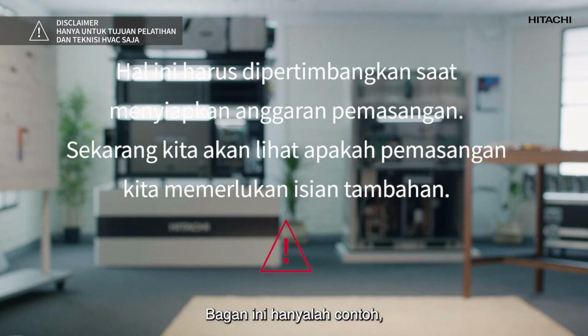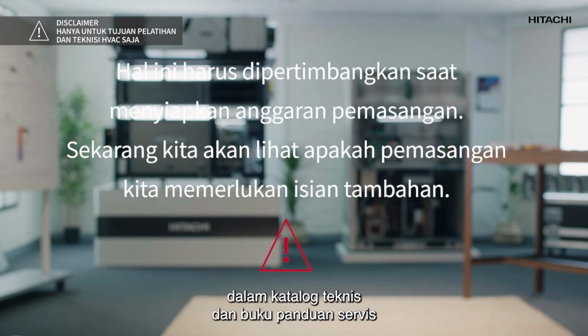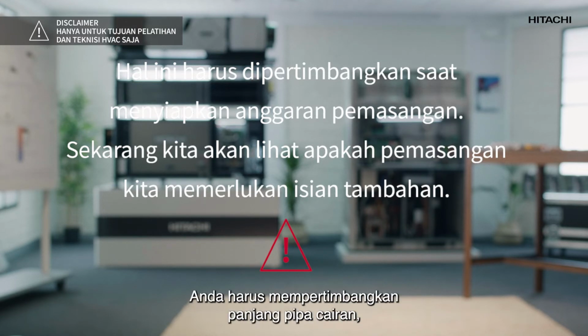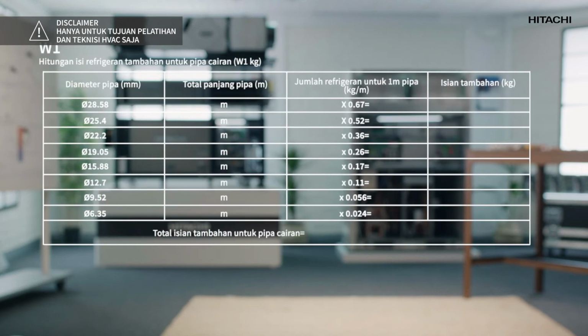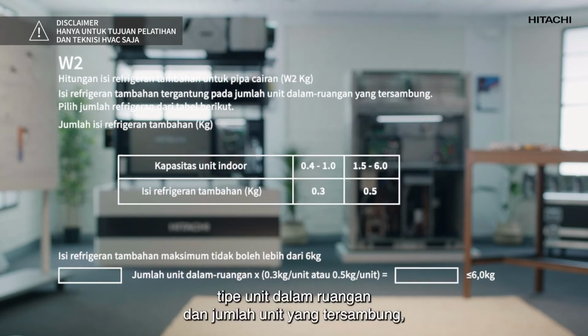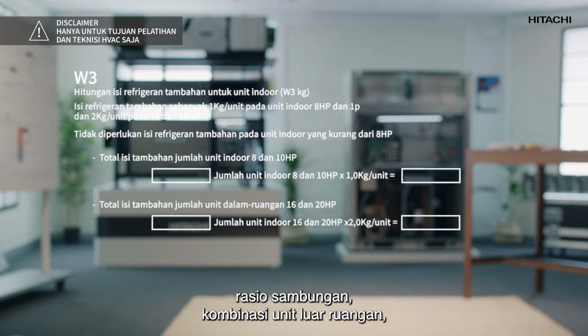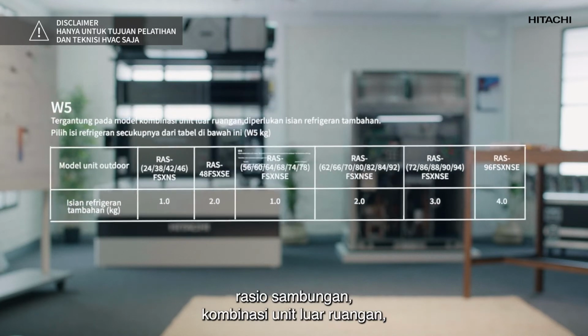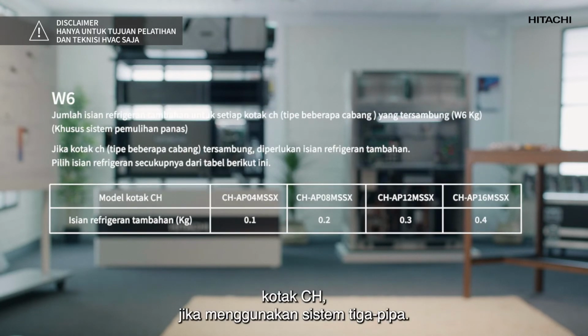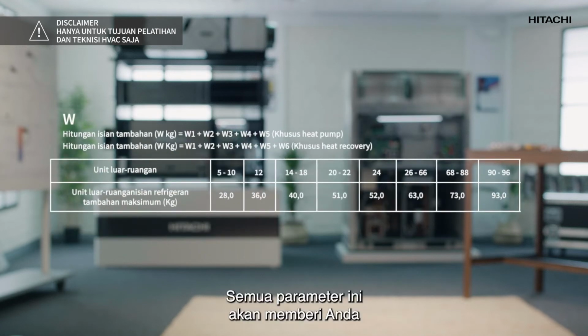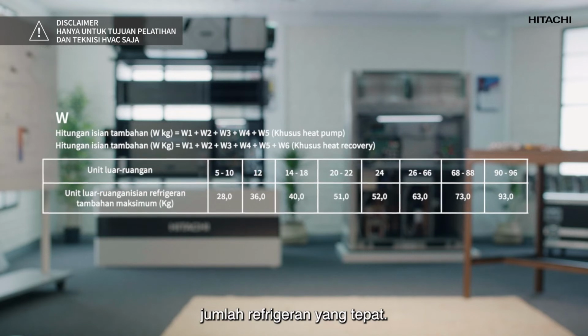This chart is only an example, but it is important to check all the charts in the technical catalogs and service manuals, because when calculating the additional charge you must take into account the liquid piping length, the type of indoor unit and the number of units connected, the connectivity ratio, the combination of outdoor units, CH boxes in case of a 3-pipe system. All these parameters will give you the exact amount of refrigerant you need.